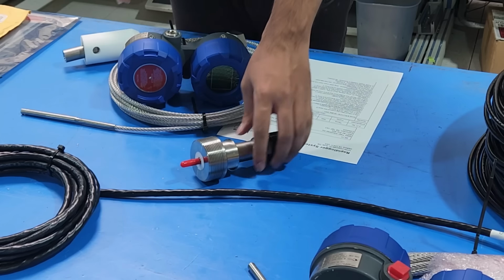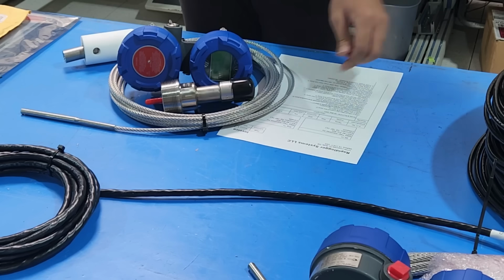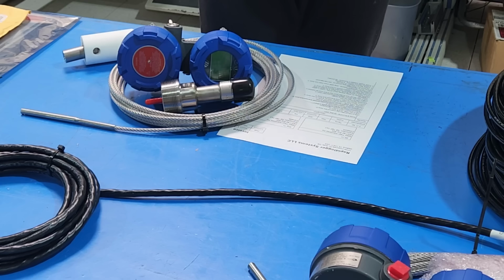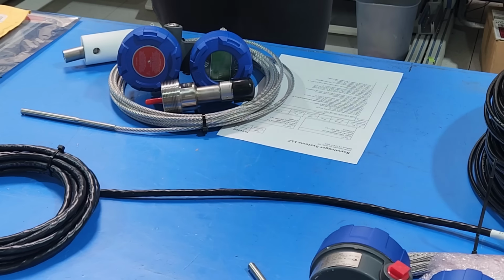The wire rope should be straight and tight between the sensor and the bottom of the tank. The level sensor sends an electrical signal down the length of the wire rope that is reflected by either the bottom of the tank or the first surface of a fluid that it encounters. This information is utilized to measure the level of fluid in the tank.